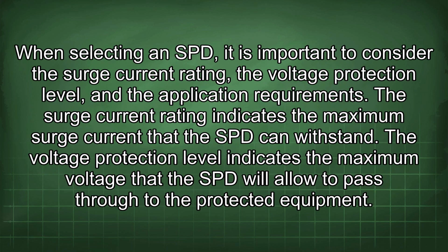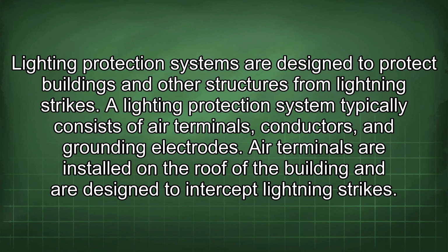When selecting an SPD, it is important to consider the surge current rating, the voltage protection level, and the application requirements. The surge current rating indicates the maximum surge current that the SPD can withstand. The voltage protection level indicates the maximum voltage that the SPD will allow to pass through to the protected equipment. Lightning protection systems are designed to protect buildings and other structures from lightning strikes.